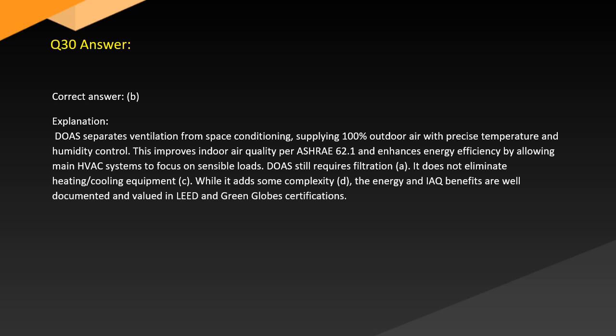Answer. Correct answer: B. Explanation. DOAS separates ventilation from space conditioning, supplying 100% outdoor air with precise temperature and humidity control. This improves indoor air quality per ASHRAE 62.1 and enhances energy efficiency by allowing main HVAC systems to focus on sensible loads. DOAS still requires filtration, A. It does not eliminate heating and cooling equipment, C. While it adds some complexity, D, energy and IAQ benefits are well documented and valued in LEED and Green Globes certifications.